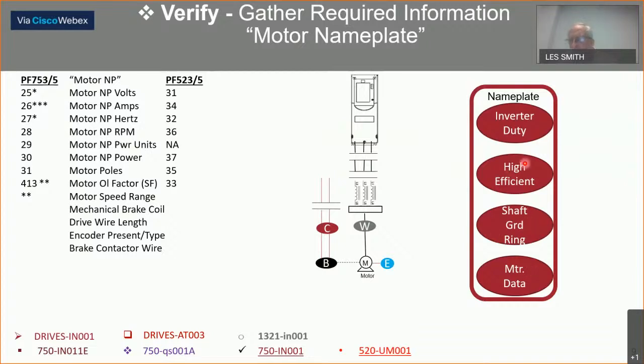I'll go back to high efficient. Some of these motors are getting very efficient. For instance, you can get a motor out there that has 1790 RPM. The drive may have trouble with that because the slip is so tight that you may have to go into a different mode than you're used to. I found that I go into the more complex modes, the vector mode, it handles those motors better. But again, just understanding what you have a hold of when you get out there to do startup.